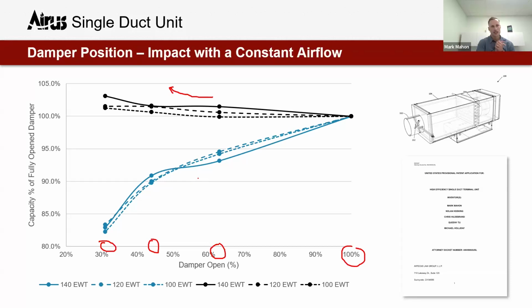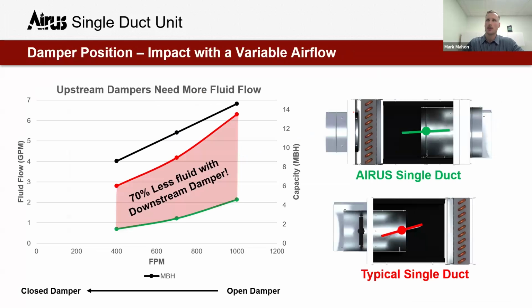A question from an attendee: does it increase the VAV box length while having a damper downstream of the heating coil? Yes, about 3.5 inches. So our original design, which you can see was filed for patent in the top right, actually maximized this length a fair bit more. But the latest version of the product, which we can see here, really minimizes it, because we found we still got about 70% of the performance improvements by close coupling the inlet to the coil. So not fully optimized, but trying to package it more like a typical single duct unit, because that's great for consulting engineers. It's good from a cost perspective. It's good for contractors who are used to seeing VAV boxes in a traditional size and shape.